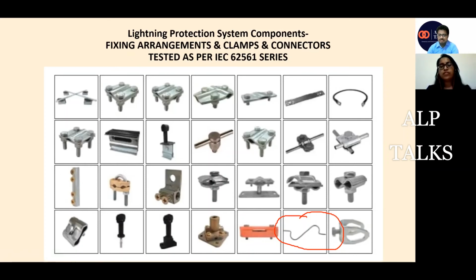Because we are using metal, whenever the environment changes, the metal will contract and expand. To compensate for that, we need to give expansion pieces at every 20 meters, so that if there is any contraction or expansion, my installation will not be hampered and the system will be protected for the longer run. These are the different fixing arrangements we use for installations, and all of these should be tested as per the IEC 62561 series.